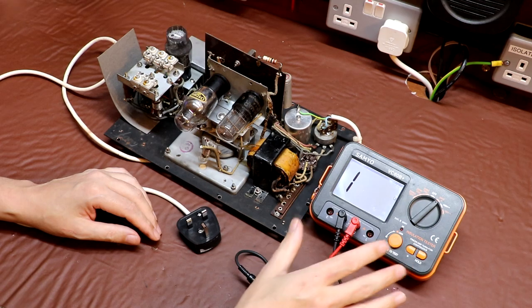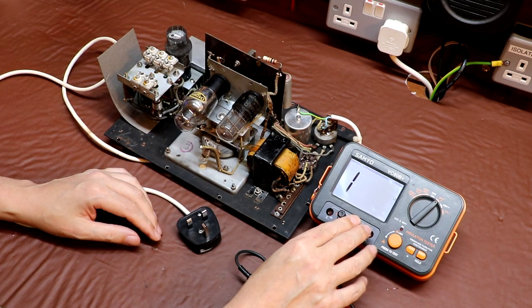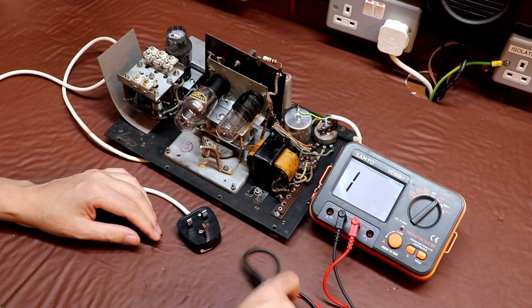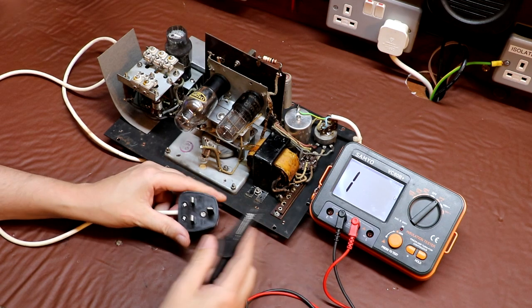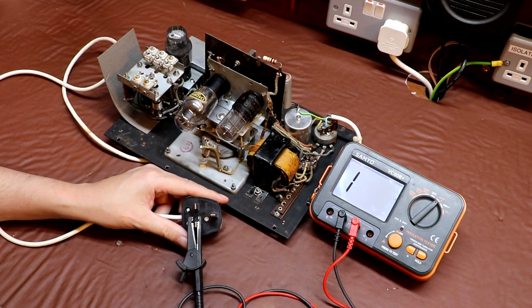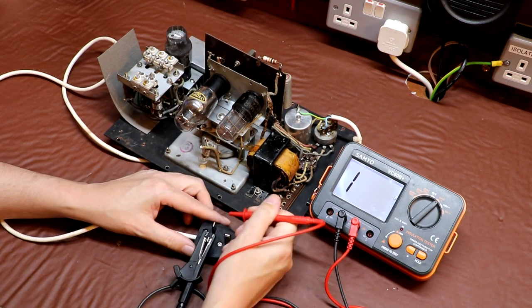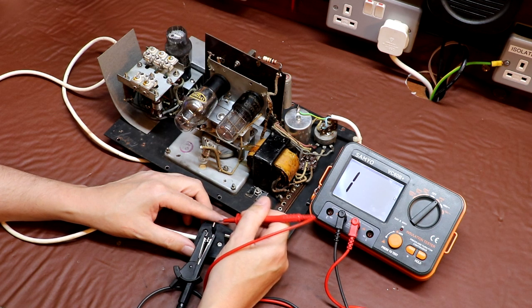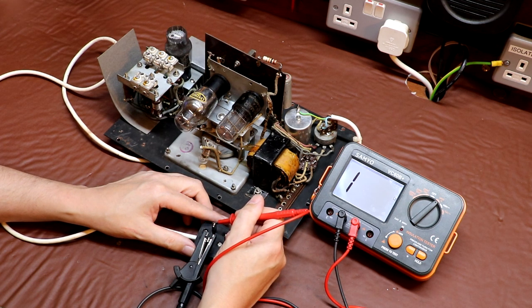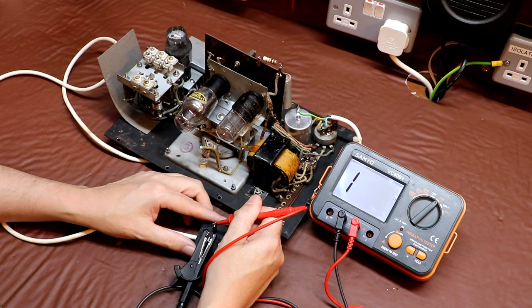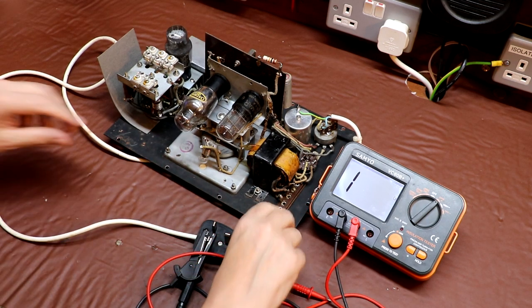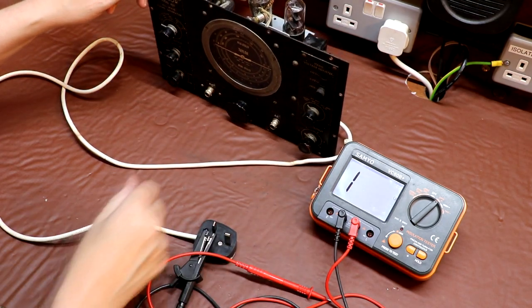So we've got our meter here. This is an insulation resistance meter, but at the moment I've got it set to the ohms range. So let's see if we can see that primary resistance of our transformer. Now, I'm expecting something probably between 100 and 300 ohms. Not exactly sure. Let's find out. Okay, we've got nothing. Okay, I'm not going to panic at the moment, because hopefully we've got nothing because the piece of equipment is switched off, which it is. Let's switch it on.